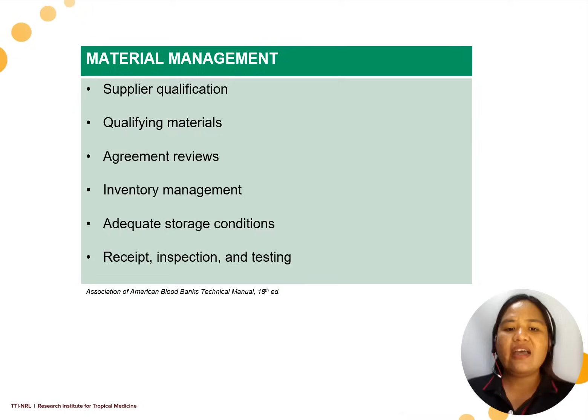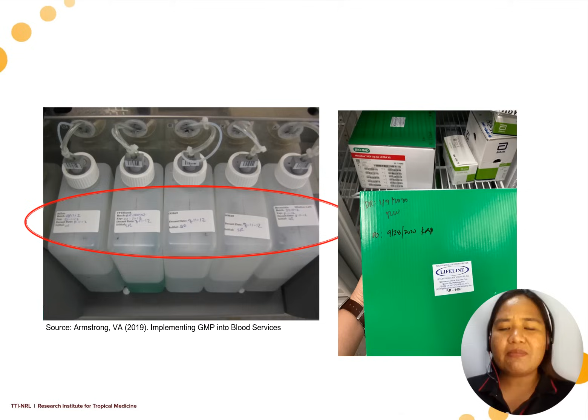And make sure that your reagents can be easily traced, no? So laboratory reagents intended for prolonged use should be marked with preparation date, expiry date, specific storage conditions, and the signature of the person who prepared them. Reagents handling must show traceability, indicate the date you first opened the common use reagents. This can be of value when you try to troubleshoot out of QC runs. Baka may problema na sa ating reagents and how it's being handled and when was it last opened, no? Reagents must be calibrated and must be valid and not expired when used. Instructions for use and storage should be followed.